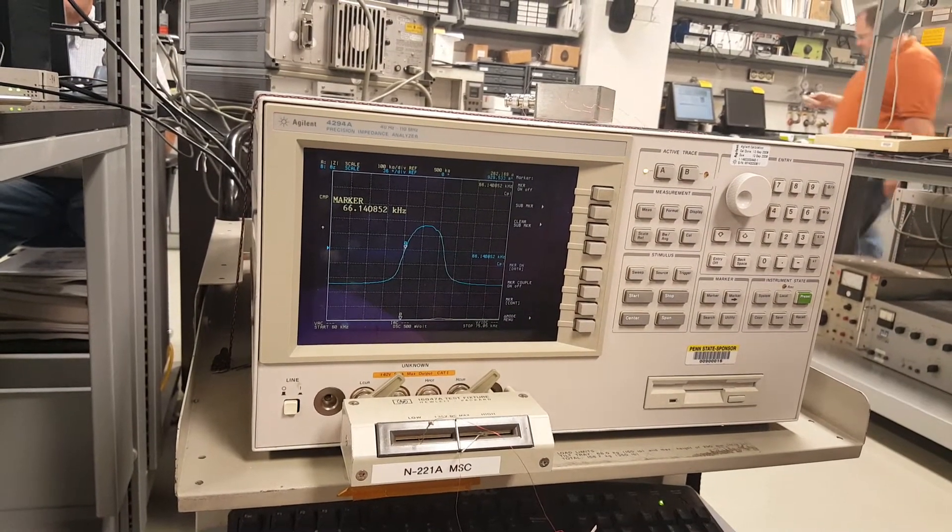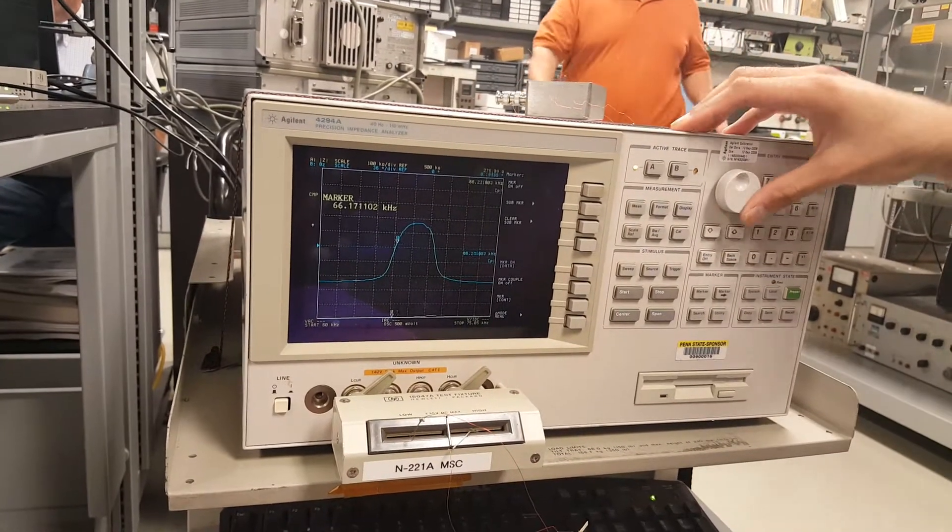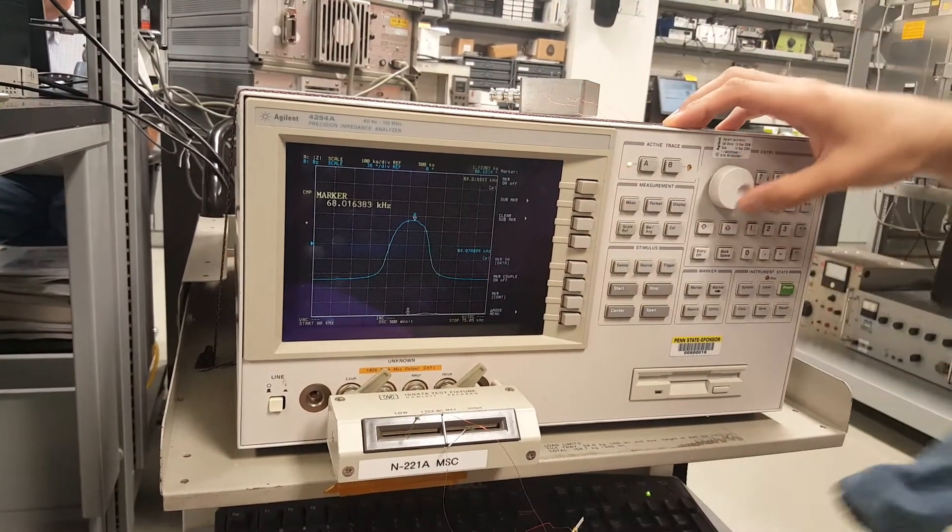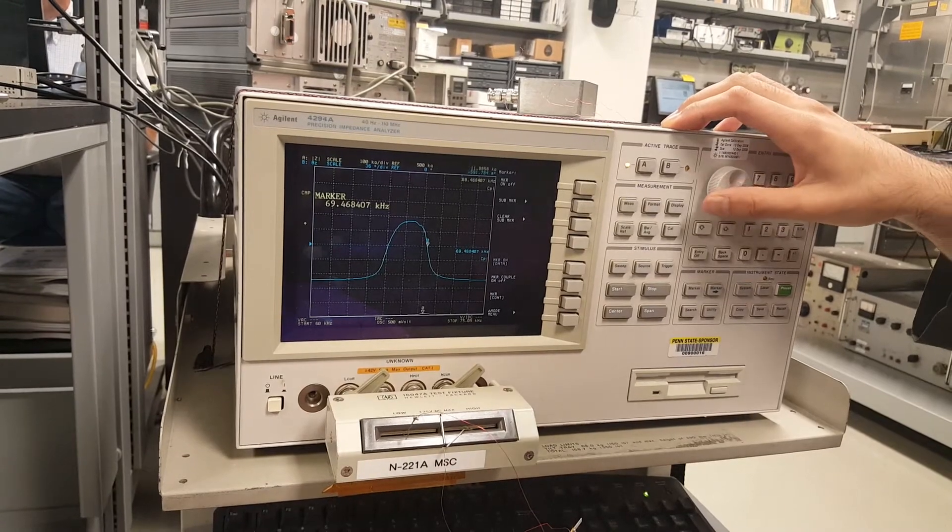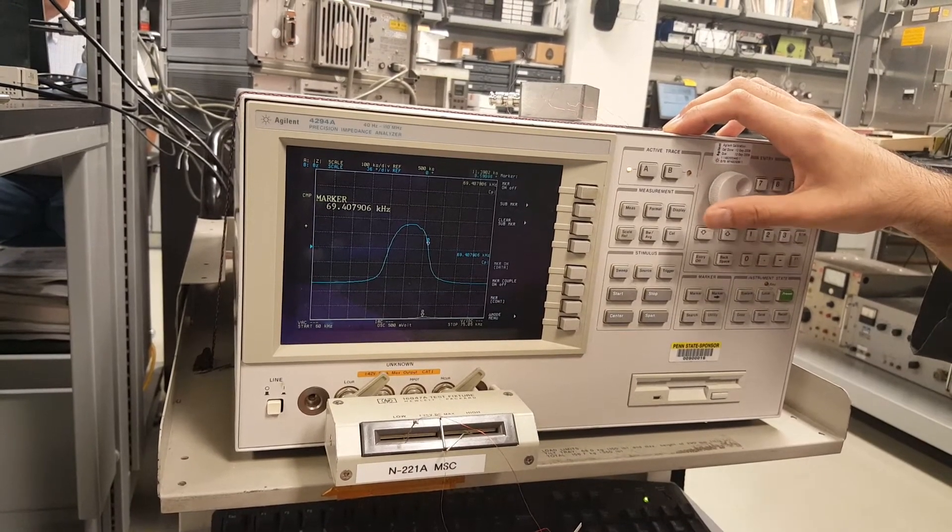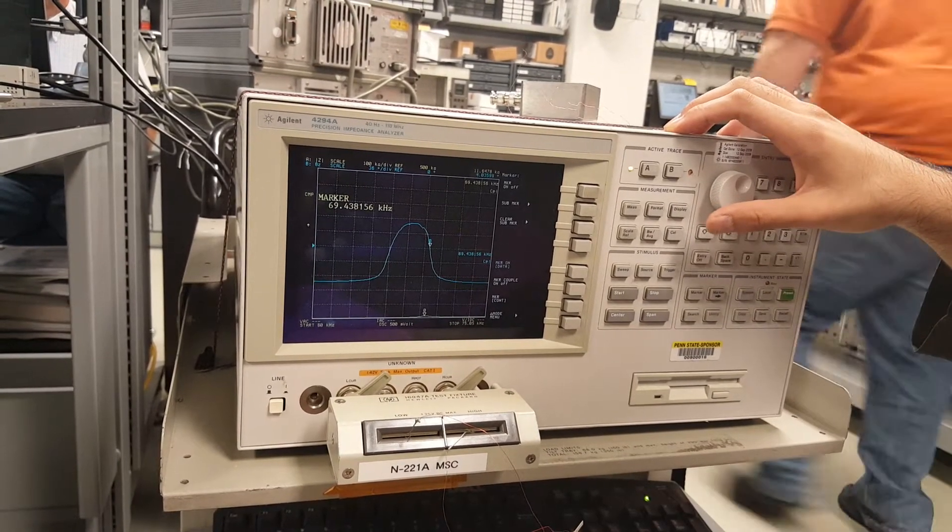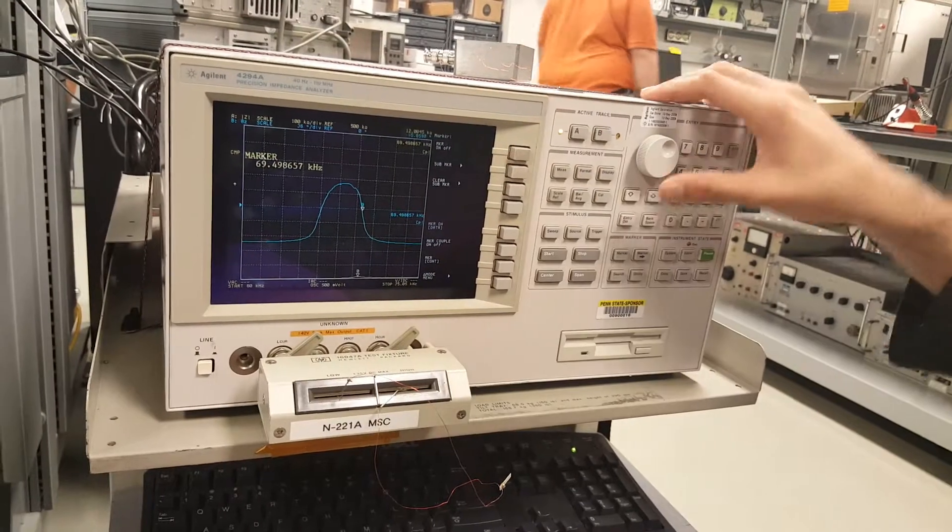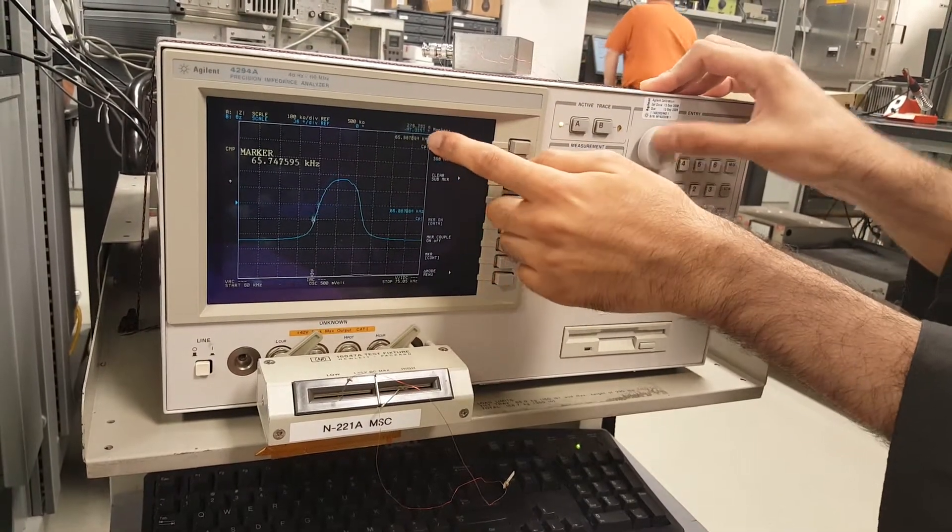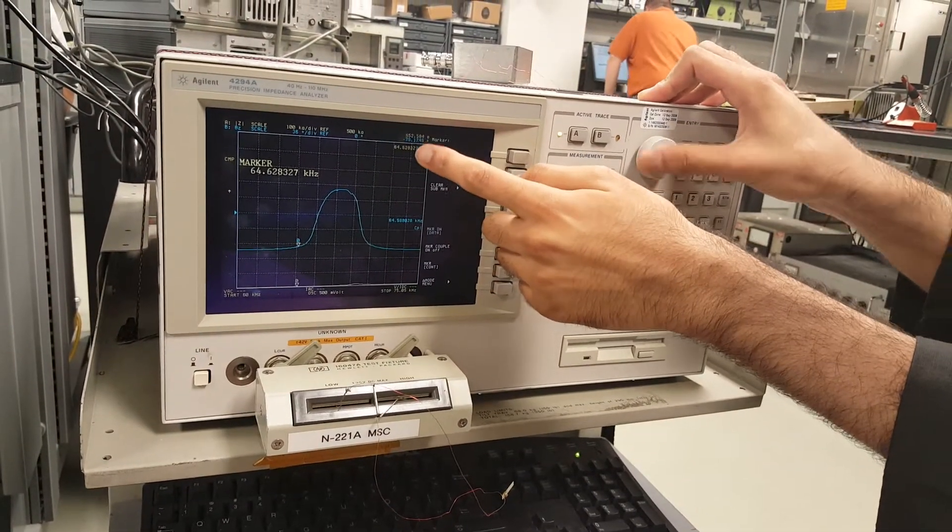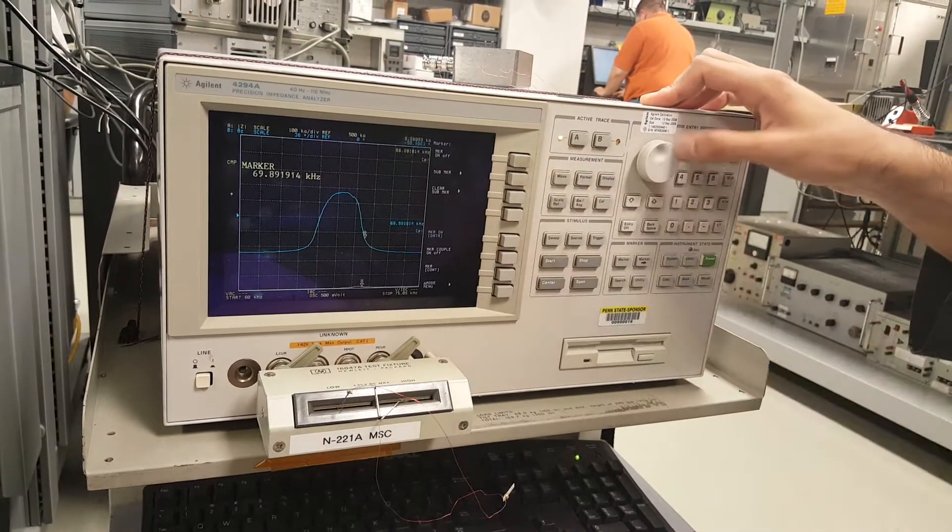So you see the phase in the top corner. This is the phase about zero here, this is about phase zero. What is this point? The resonance. Yeah, it's the resonance, and then the phase becomes 90, and then it goes back down to anti-resonance. So what is this point in the phase? The anti-resonance. And you can sort of see in the corner it's telling you the impedance value and it's telling you the phase value in blue.